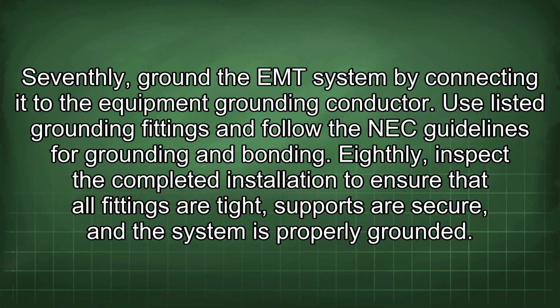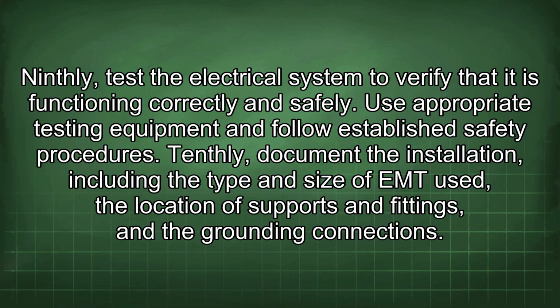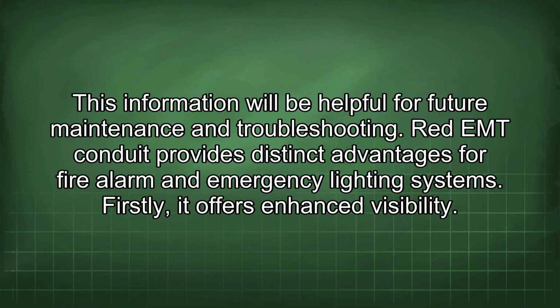Eighthly, inspect the completed installation to ensure that all fittings are tight, supports are secure, and the system is properly grounded. Ninthly, test the electrical system to verify that it is functioning correctly and safely. Use appropriate testing equipment and follow established safety procedures. Tenthly, document the installation, including the type and size of EMT used, the location of supports and fittings, and the grounding connections. This information will be helpful for future maintenance and troubleshooting.